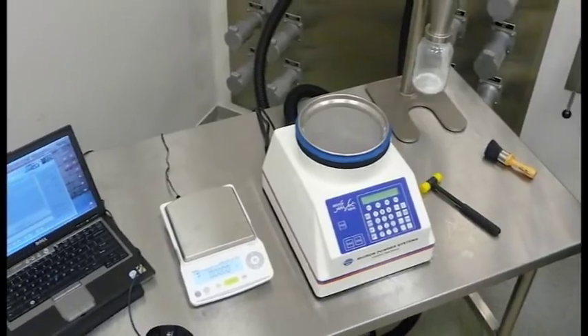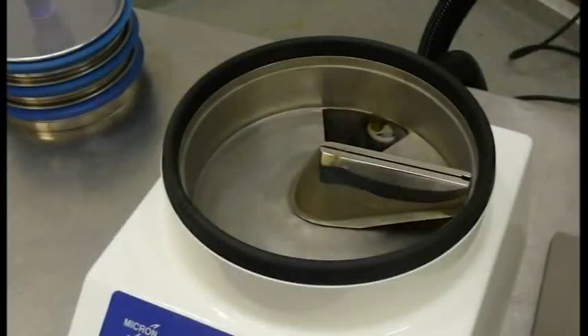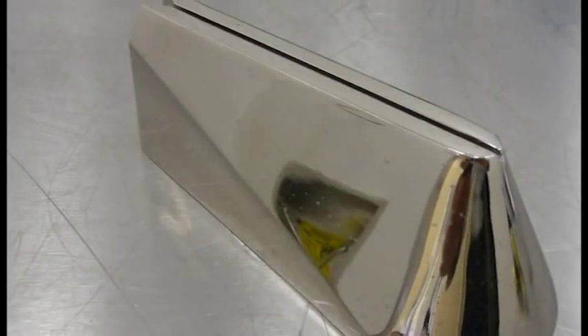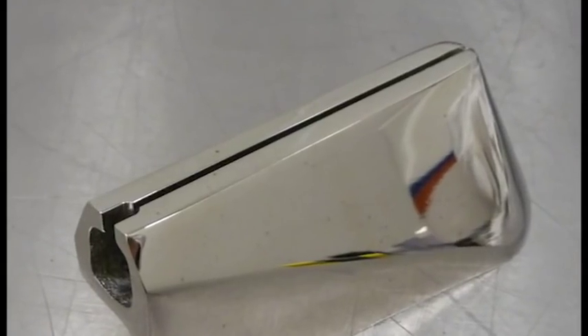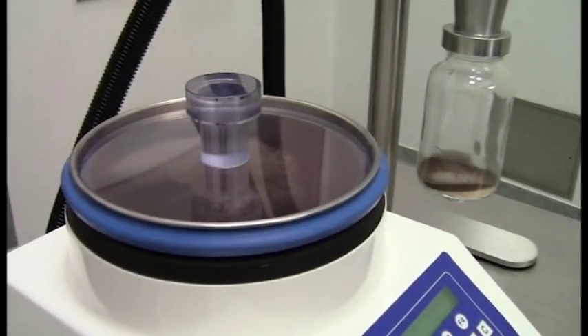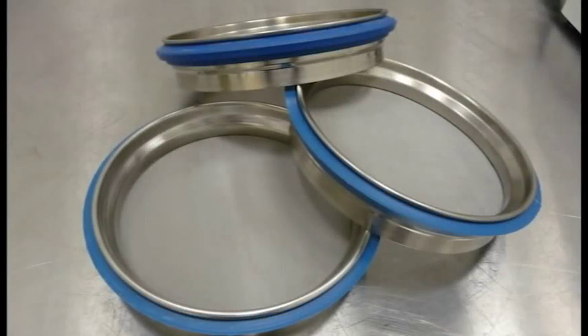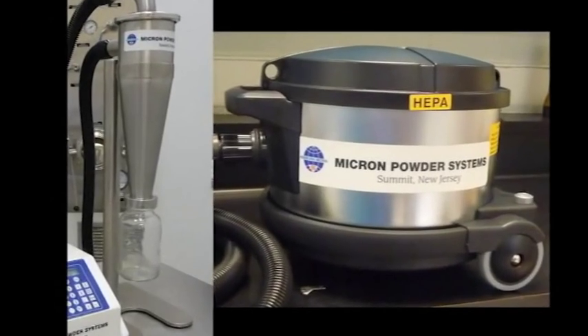A positive airflow is introduced through a rotating wand beneath the test sieve screen, while a negative pressure airflow carries particles small enough to pass through a defined particle size test sieve screen to a collection device.